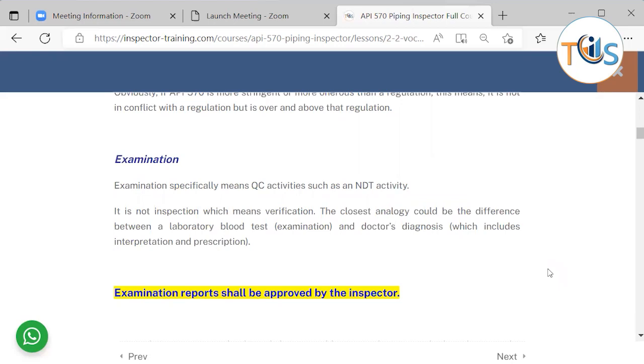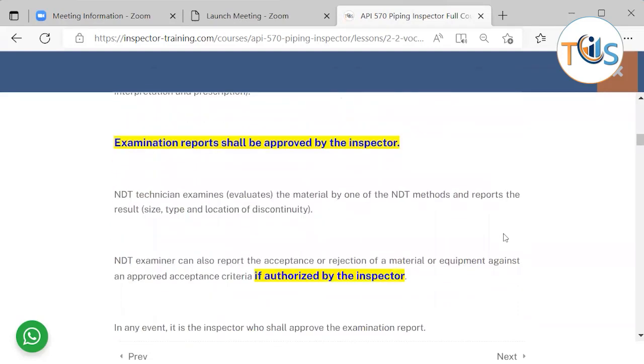Examination means QC activities such as NDT activities — it is not an inspection. Inspection means verification. An examination is one of the QC activities. The analogy could be like a laboratory blood test being the examination, while the doctor's diagnosis, interpretation, and prescription represent inspection. Examination reports shall be approved by the inspector.